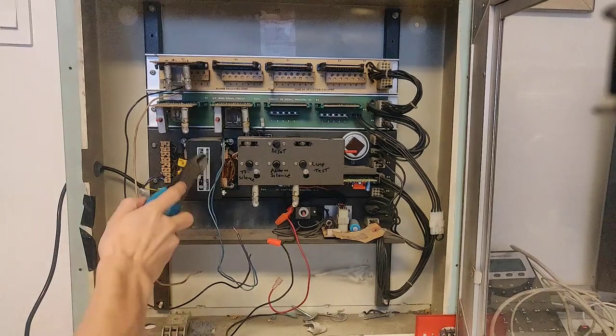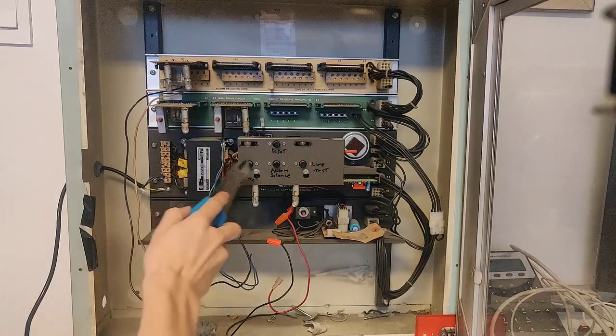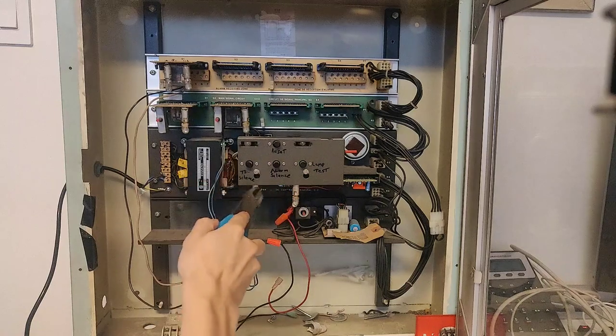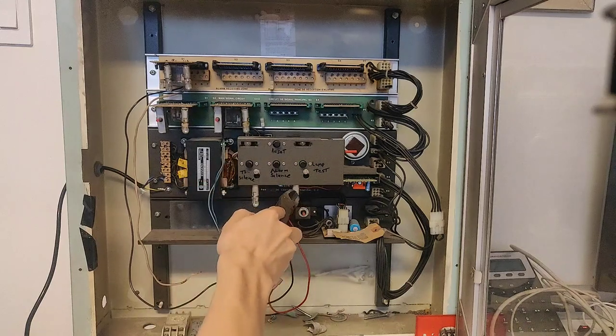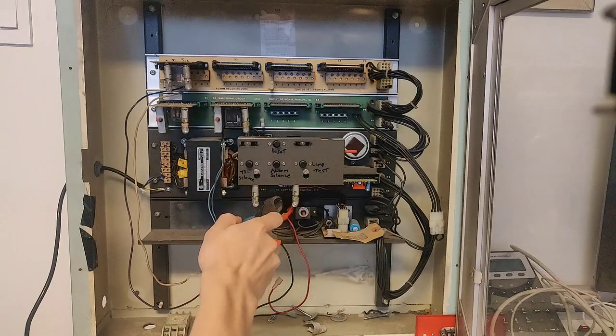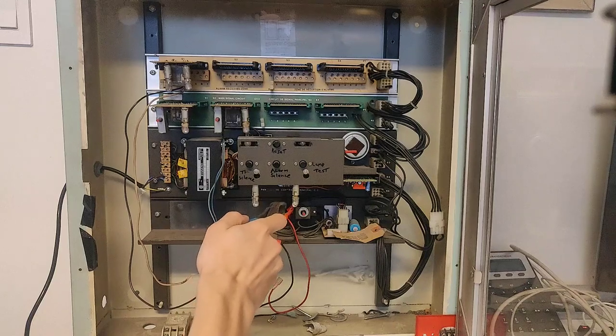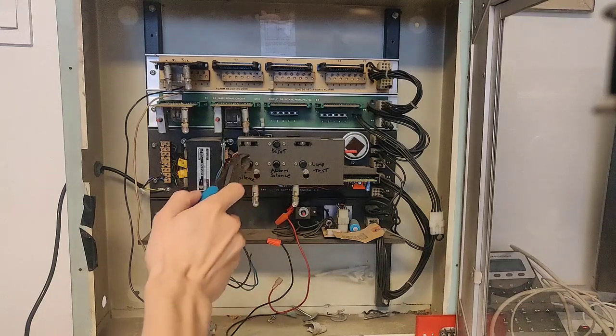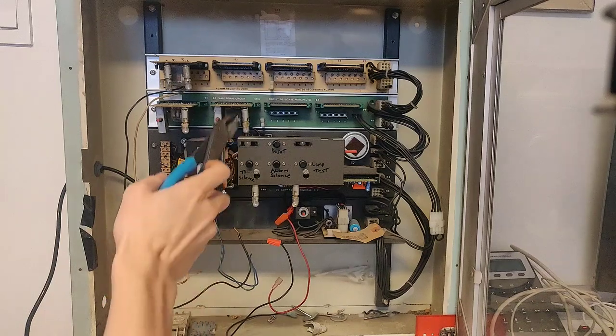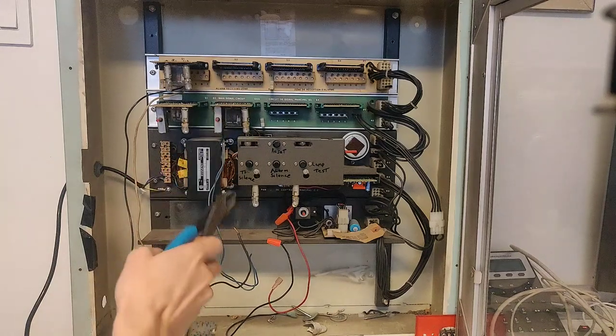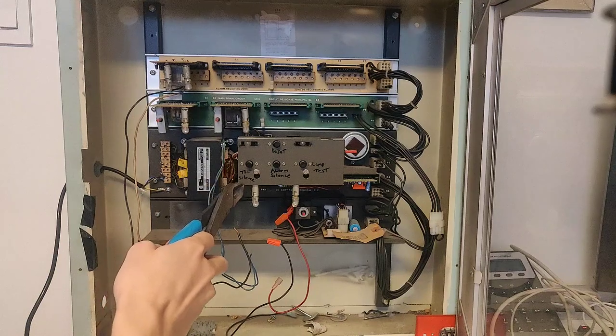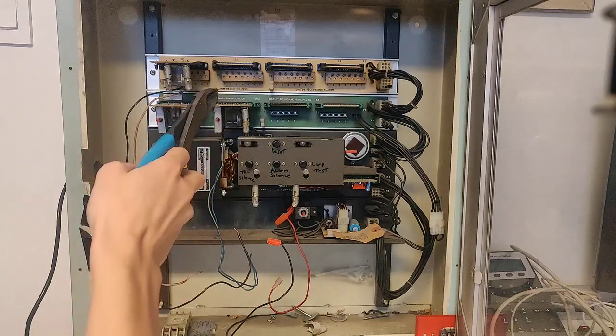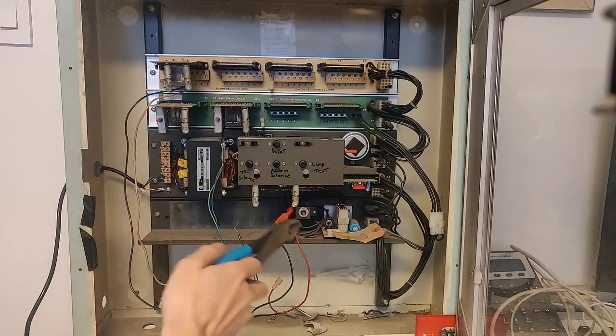So this is our main power transformer. These are the controls and main lights including the ground fault light. One thing worthy of note: older 6500s have no ground fault detection. Some of them have limited ground fault detection, meaning they can detect ground faults on the alarm zone only or the signal circuit only. And I believe this model can detect ground faults on both circuits. So that's pretty nice.